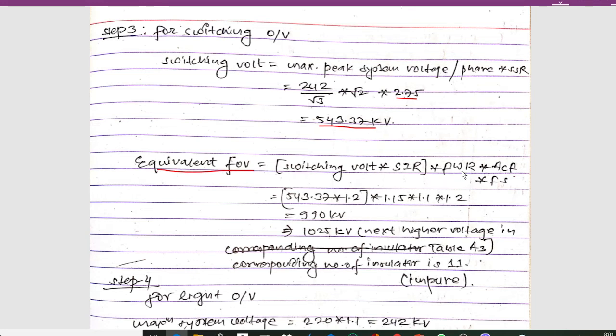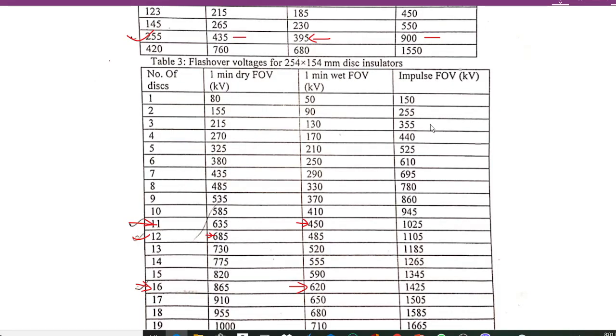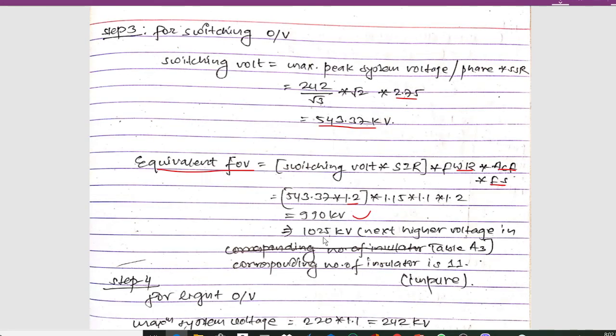This gives a switching voltage of 543.37 kV. The equivalent flashover voltage = switching voltage × SIR × FWR × ACF × FS. Substituting 543.37 × 1.2 × 1.15 × 1.1 × 1.2, we get 990 kV. From Table 3, checking the impulse column, the next higher voltage above 990 kV is 1025 kV, and the corresponding number of insulator discs is 11.